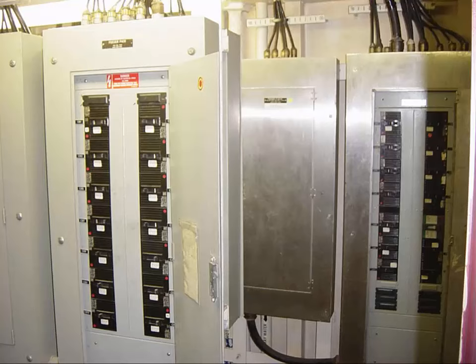And then you have your different power panels throughout the ship, some for lighting, some for small motors, and these also are going to protect those individual circuits. So one thing of note, when you talk about distribution, your main switchboard has a very high load carrying capability. And then those have breakers that protect equipment, and the size of the cabling is a determinant on this going to each of these pieces of equipment.